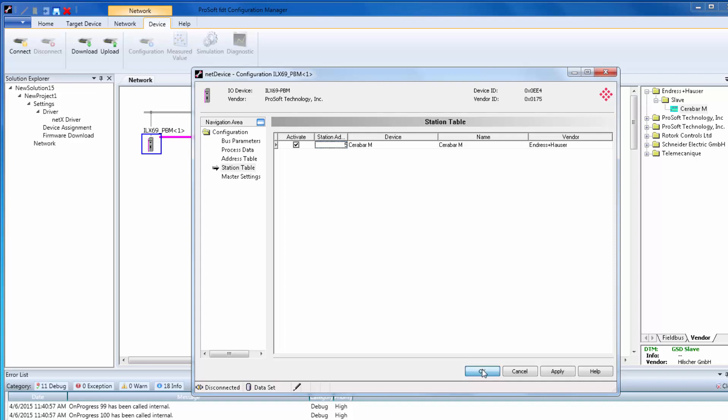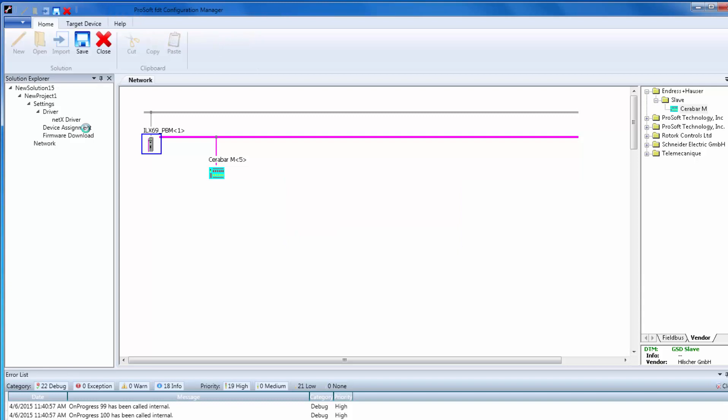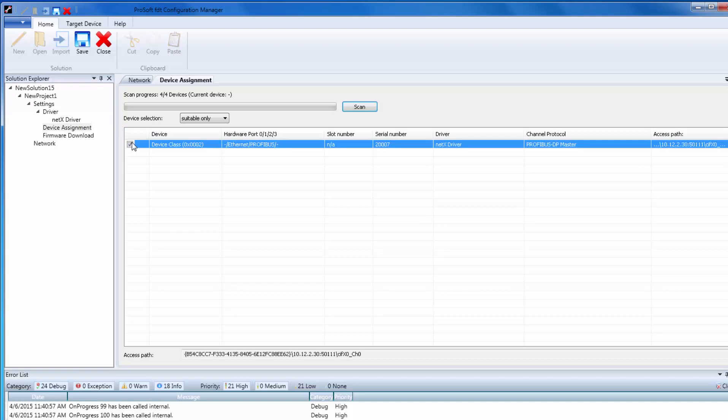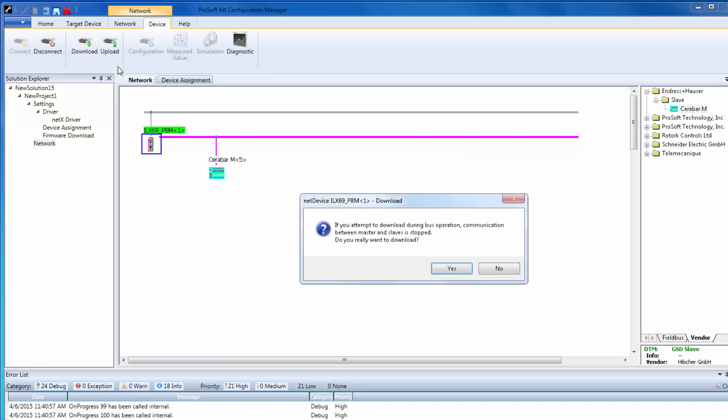Once all configuration is done, we can download to the Profibus master. To download to the module, we must assign the software to the hardware. To do this, click on the master, then choose Device Assignment on the left pane. Find your module and check the checkbox. Now go back to your network. Your device is now assigned to the hardware. Highlight the master, then click on the Device tab, then click Download.